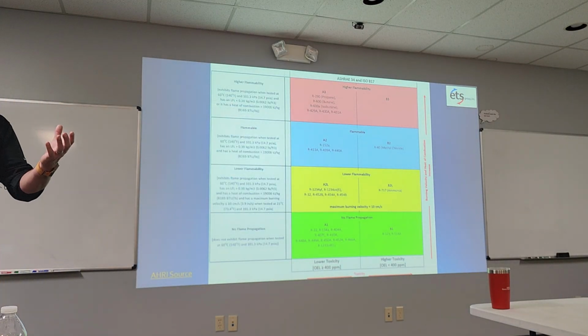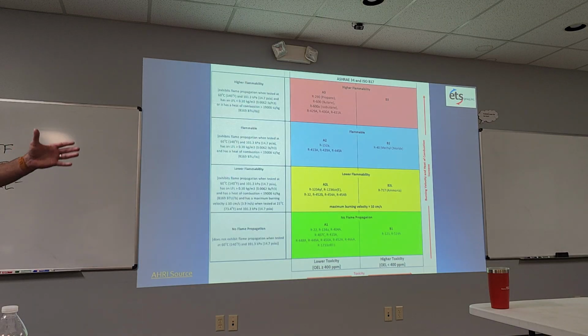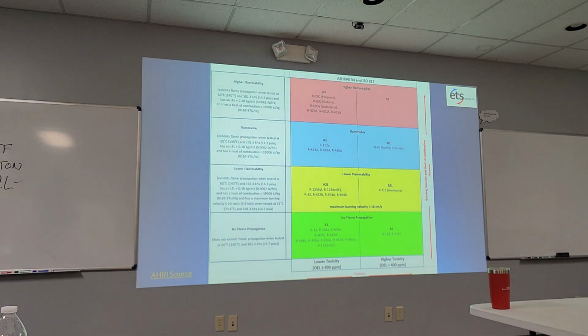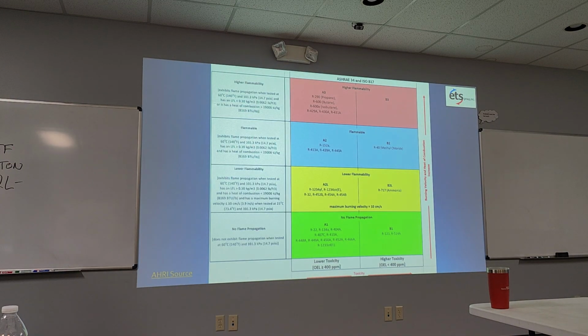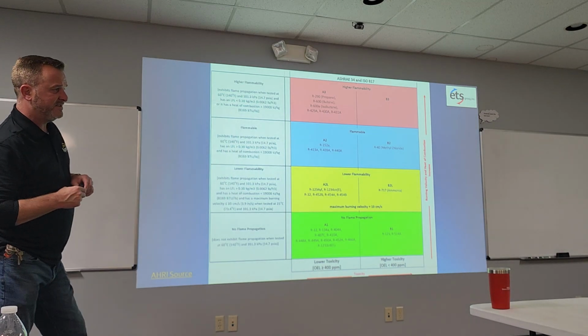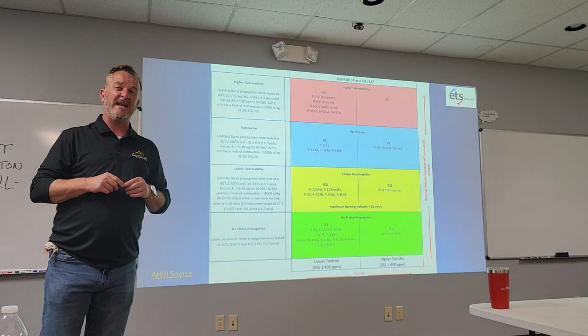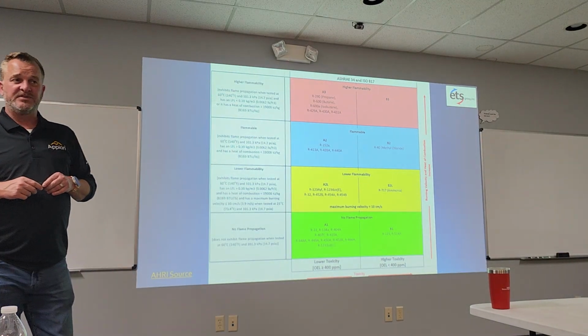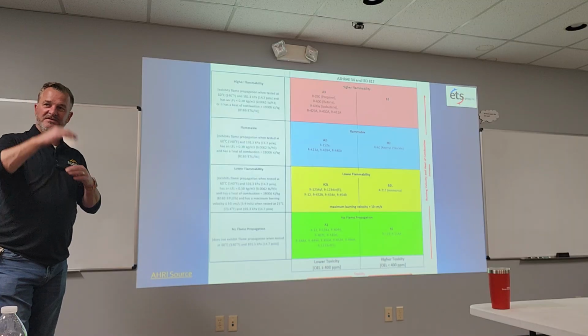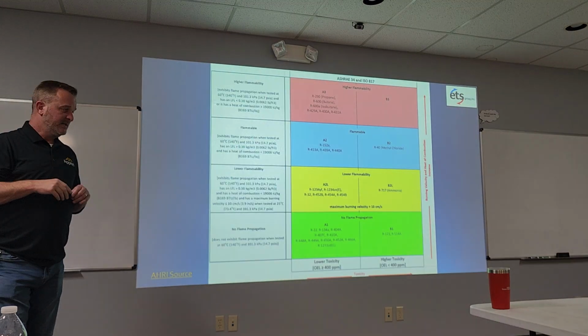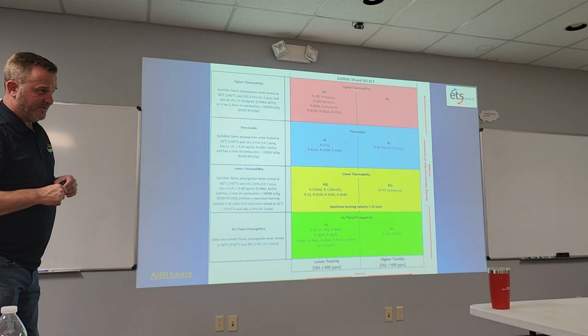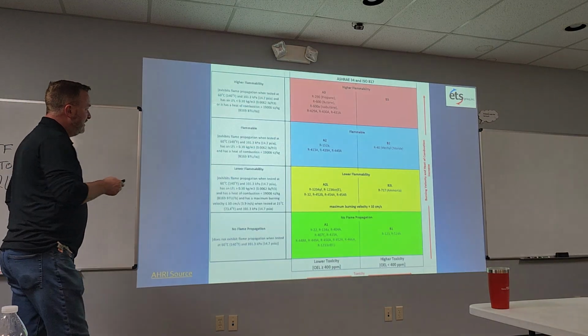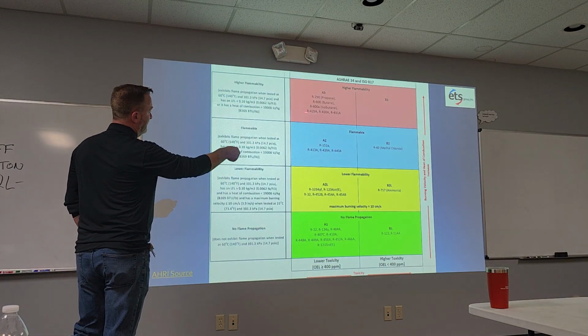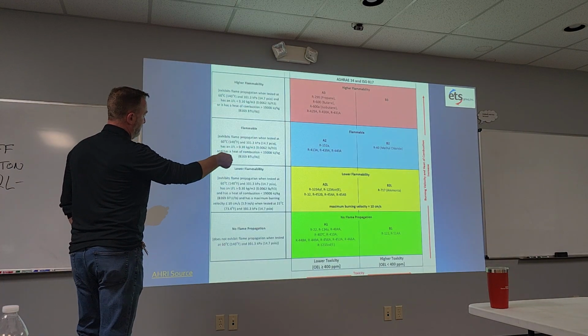What are those used for mainly? Smaller systems. Up to just a little bit ago, I think the most concentration you could have in a system of an A3 refrigerant was 5.8 ounces. I've heard for some commercial applications you can get up to 12 to 15 ounces, but there's not a lot of this refrigerant in there. Your A3s and your B3 refrigerants, those are your higher flammability.